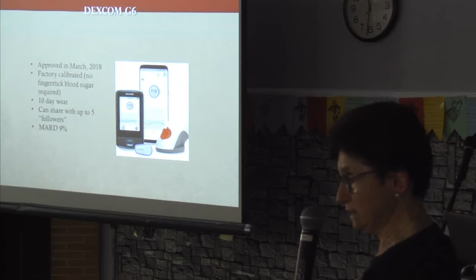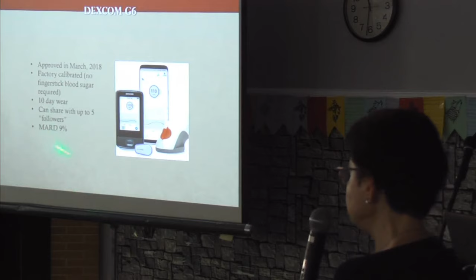So when you calibrate the device with something that's already not accurate, obviously the sensor is not measuring that accurately either. But if you do the super accurate calibration, ideally, that would be the MARD. The actual MARD is better than the meter.